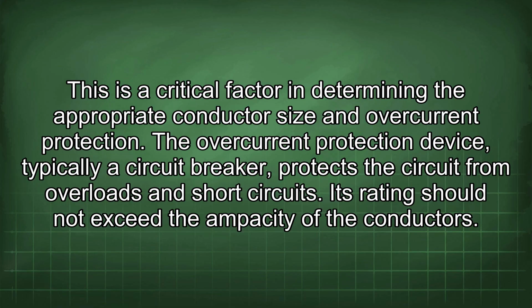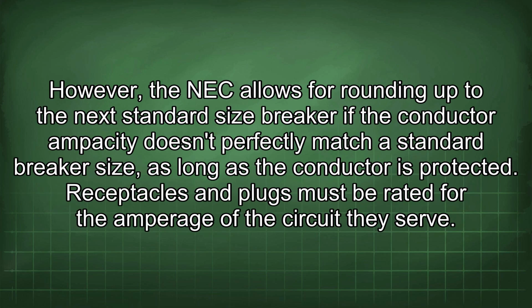The overcurrent protection device, typically a circuit breaker, protects the circuit from overloads and short circuits. Its rating should not exceed the ampacity of the conductors. However, the NEC allows for rounding up to the next standard size breaker if the conductor ampacity doesn't perfectly match a standard breaker size, as long as the conductor is protected.